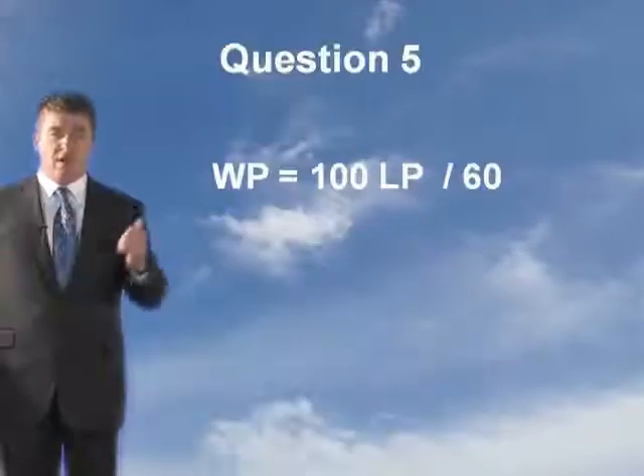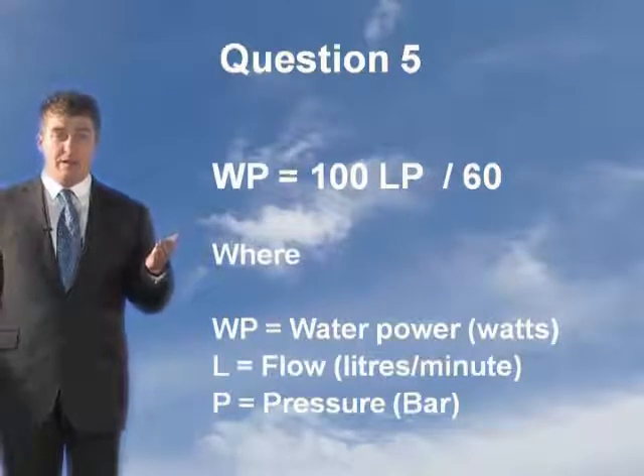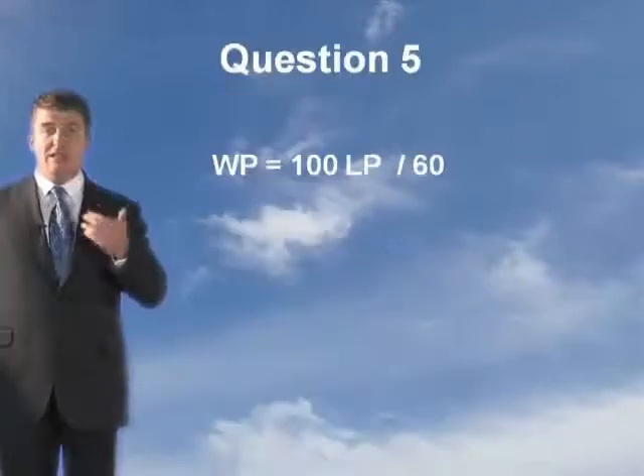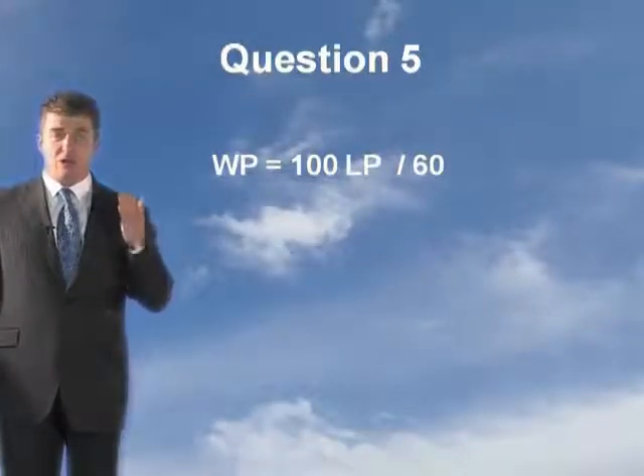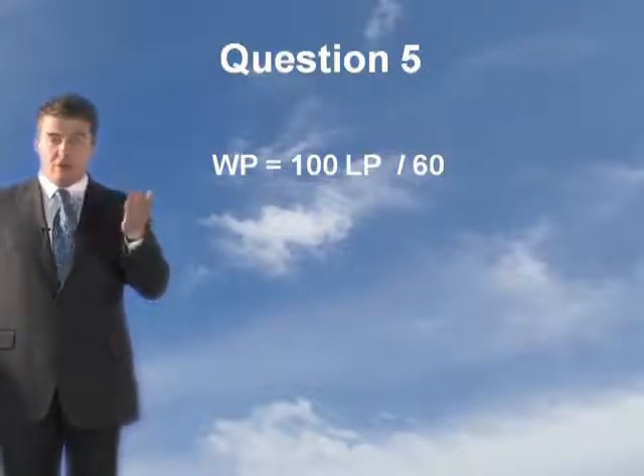Now what's the first thing we're going to do? We need to work out the pressure at the outlet. This is where you have to bring in another hydraulic formula: water power equals 100 LP divided by 60. WP is the water power, L is the flow in litres a minute, and P is the pressure. Using this formula, WP equals 100 LP divided by 60, we need to get P to be the subject of the equation, so you need to transpose it.